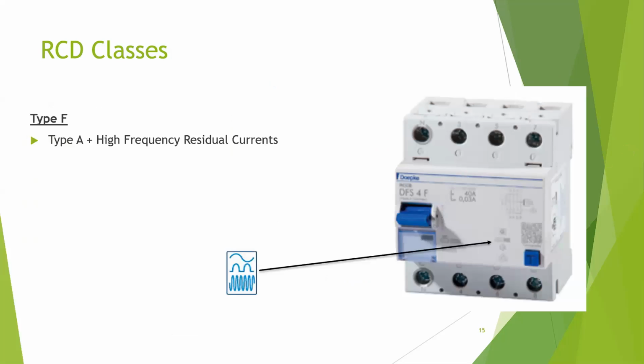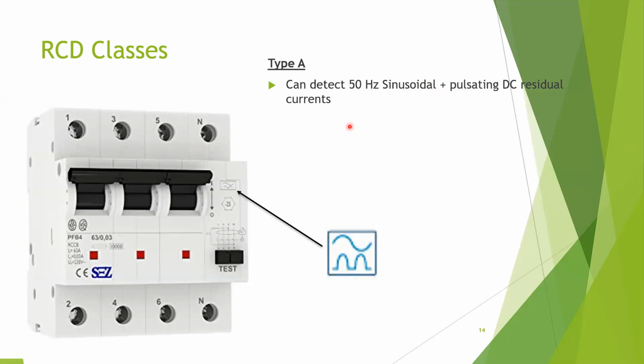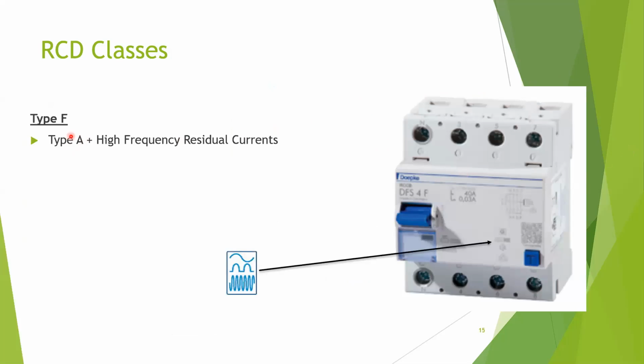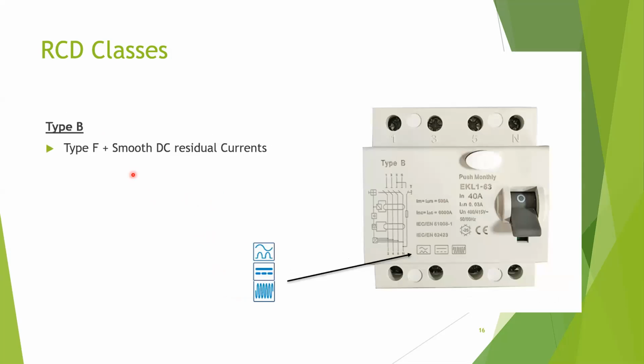Okay, type F, high frequency. This one can detect everything that type A can detect. That means 50 hertz sinusoidal and pulsating DC, and additionally high frequency residual currents. High frequency residual currents are a bit important because when you have solar, there are high frequency residual currents in your house. This is not very important for solar installations in Sri Lanka because those are grid tie units. If you have hybrid units, you should have one of these kinds of RCDs. And type B can also detect imbalances in smooth DC residual currents.